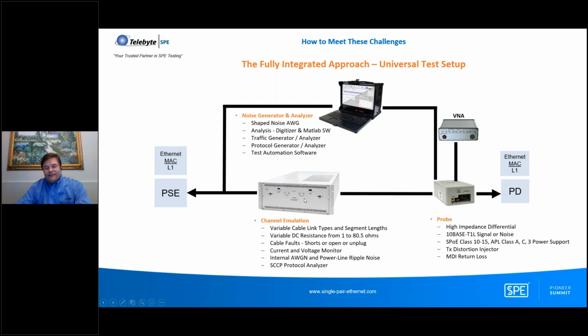And we can also analyze the classification protocol, the serial communication classification protocol. So the PSE device talks to the PD device. We can monitor that communication, where the PSE determines what power the PD needs. Then we have a high impedance differential probe on this end. In this example, we're testing the powered device, and we can capture the transmit and receive signals from this device. If we take the device out and terminate, we can also capture the noise on the cable. So if there's noise in a setup, we can capture it. It supports all classes for power for the 802.3cg and advanced physical layer, and it also includes the distortion injector.